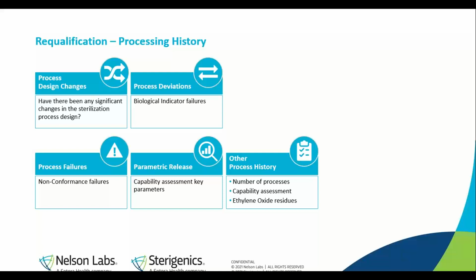The last phase of the requalification review involves the process history. Are there any process design changes to the sterilization process? For example, is there a change to the process temperature, any change to the steam addition phases, or the gas exposure time, or any evacuation changes? The next portion of that review would be any process deviations, specifically any biological indicator failures identified since the previous requalification. We'll talk about that a little bit more in depth later.